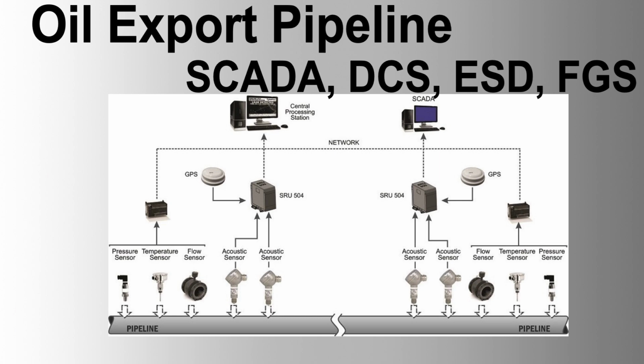3. Emergency Shutdown System, ESD. Function: ensure safety by initiating shutdowns during abnormal conditions to prevent damage. Design aspects, independence: standalone system with SIL-certified PLCs, independent of ICS and FGDS systems. Objectives: prevent serious damage to human life and pipeline infrastructure, facilitate isolated shutdowns. Functions: emergency shutdown functions, continuous monitoring of critical process IOs, communication with ICS for secondary actions. Interface: displays status on ICS process graphic displays, maintenance bypasses applied through ICS HMI.